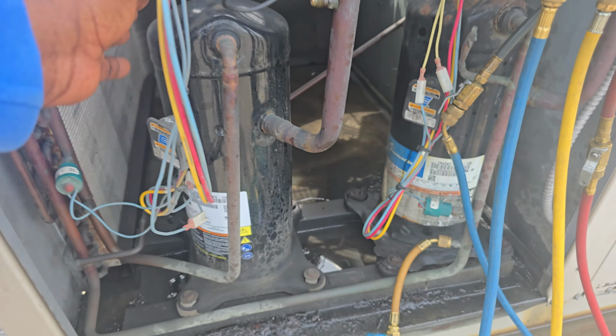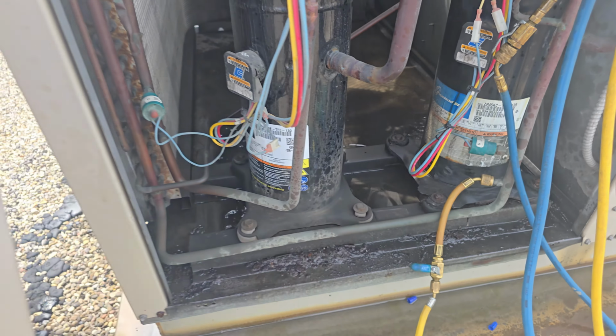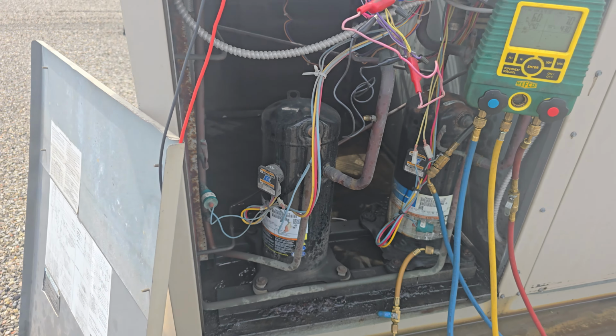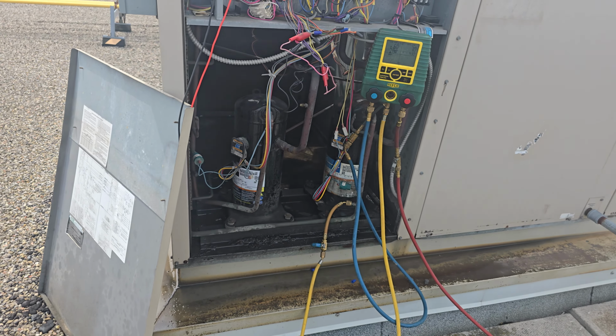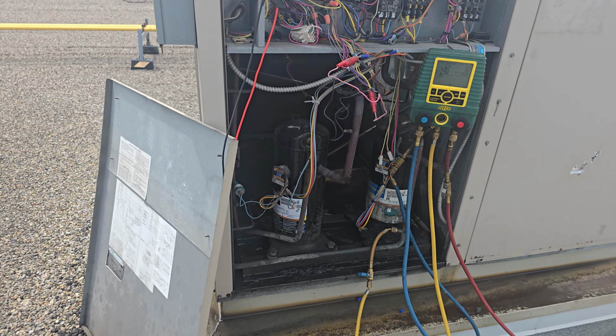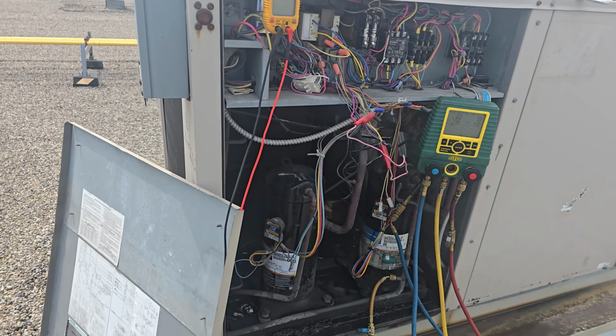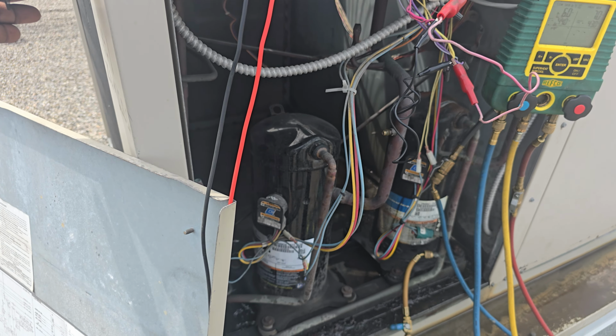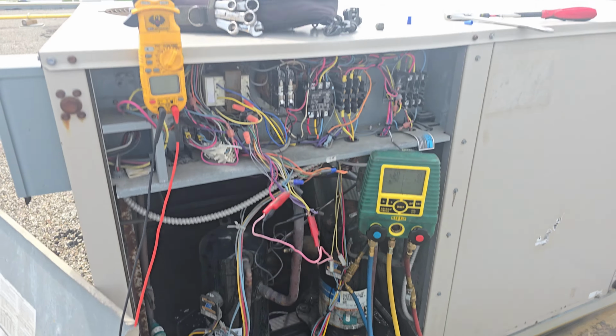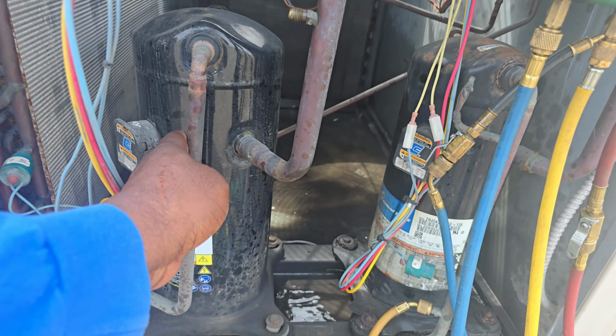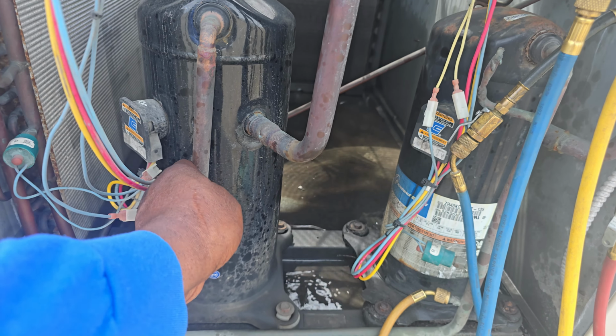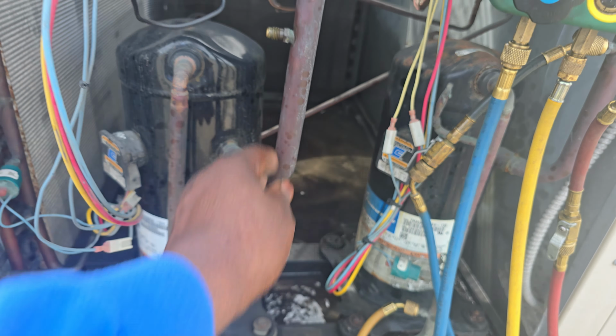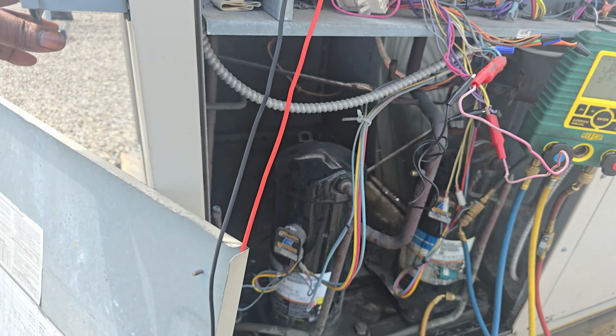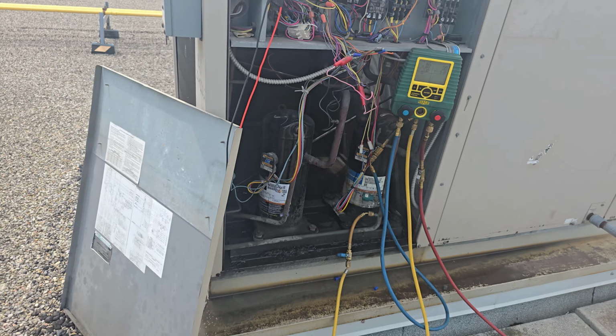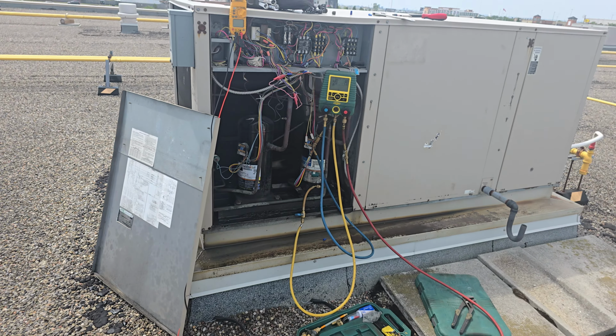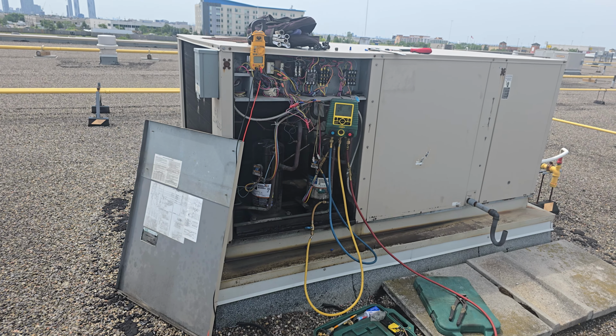I just want to make sure this compressor works, and also make sure if there is a little bit of gas inside. I am not putting in my gauge. I'm just going to do a quick test. So I'm going to turn on the unit. My condenser fan comes on. I can see my compressor warming up really good. So that's good. I'm not going to stay that long, this is just a quick test. So my compressor number 2 is okay.